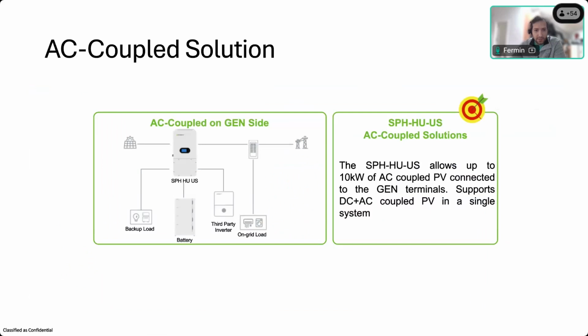It also allows you to connect a third-party PV system. So this is what the AC coupled solution looks like. This allows you to connect a third-party PV system to the generator ports, up to 10 kilowatts of AC coupled PV on the gen ports. This basically allows you to control the third-party PV system more easily to avoid any overloads or any damage to the inverter. It also has over frequency control to adjust the output of the third-party PV system. But in case it's needed, the inverter is able to cut off the power completely from the third-party PV system.